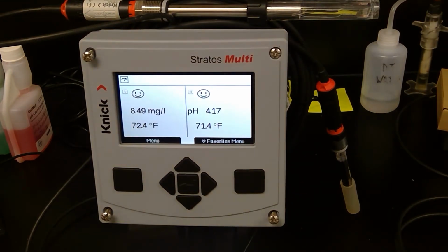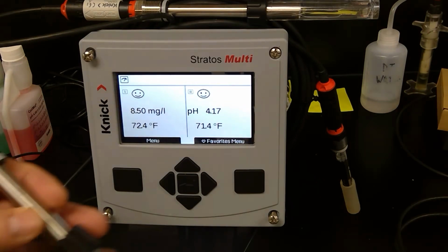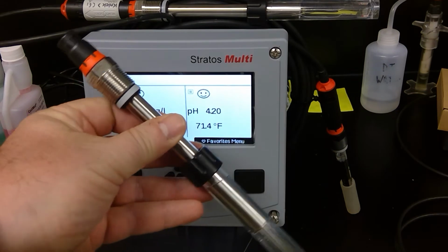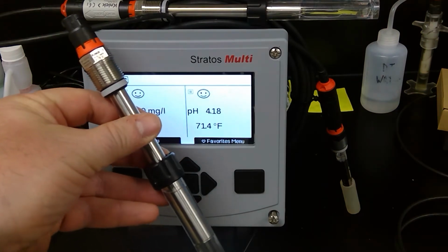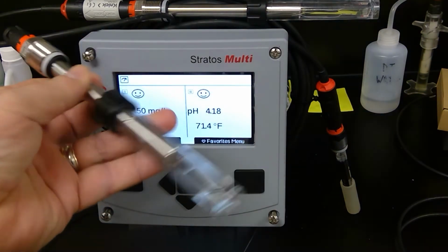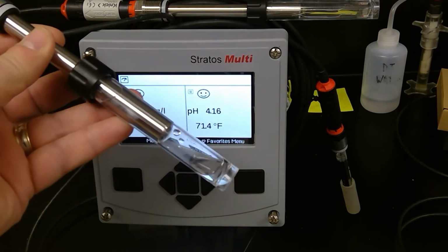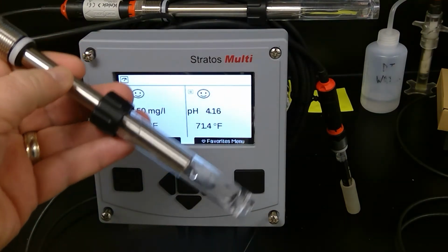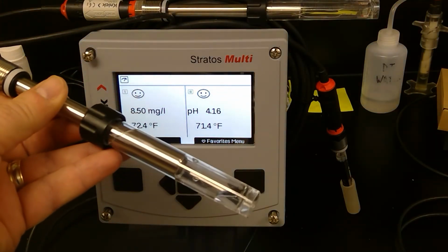Hello. In this video, we're going to go through a basic calibration for an amperometric Clark-cell dissolved oxygen electrode. Here's an example of the type of electrode I'm talking about. This one happens to be an SE706 with a membrane cap on it. So again, this is not a luminescent dissolved oxygen sensor. This is an amperometric Clark-cell design.